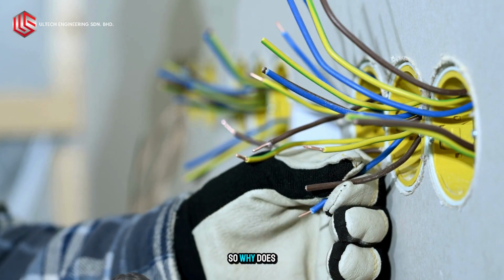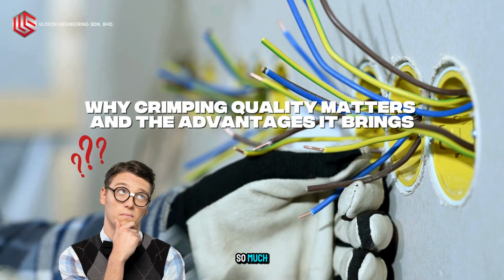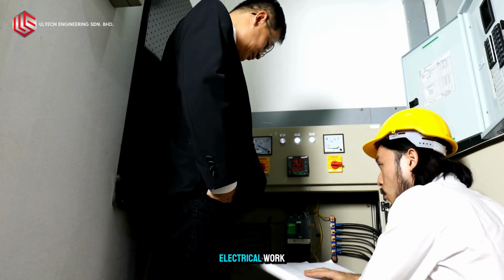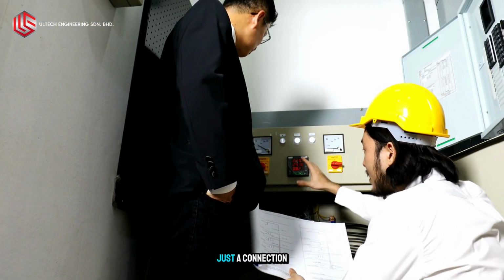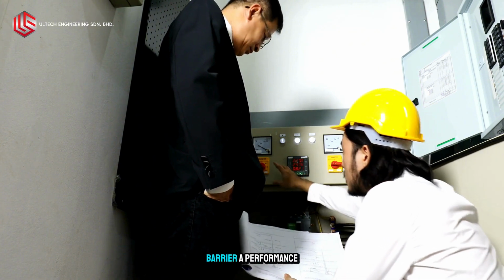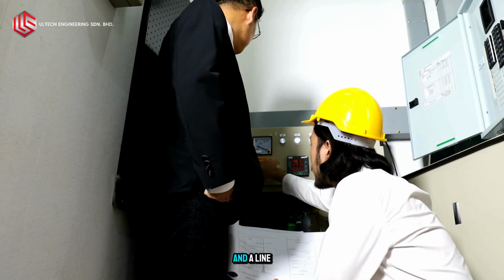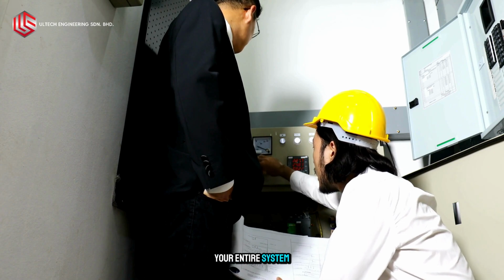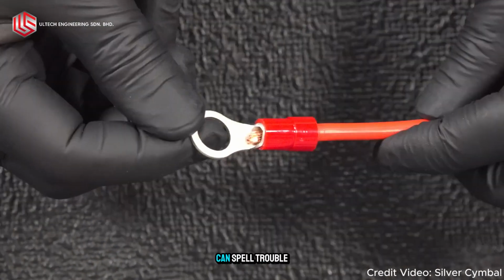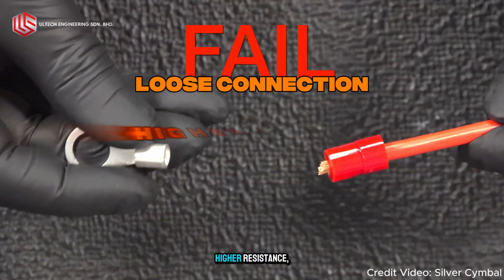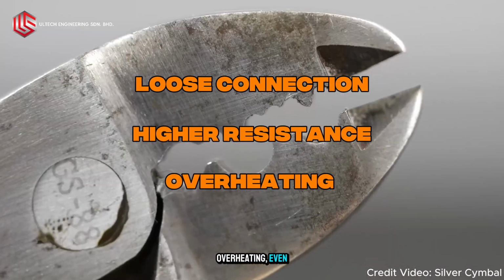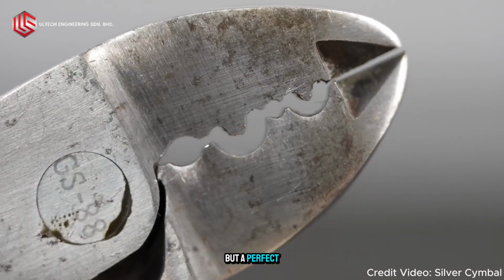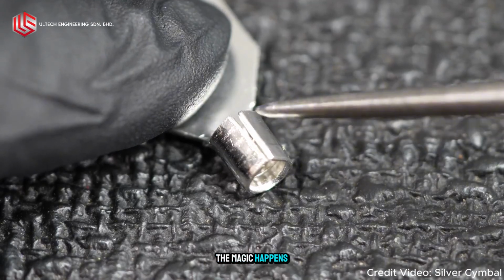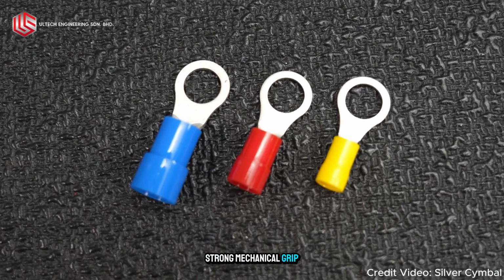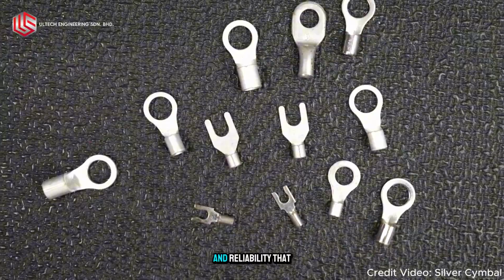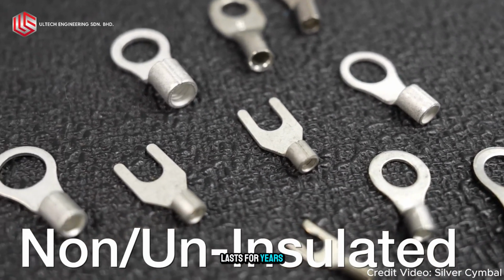So why does crimping quality matter so much? Because in industrial electrical work, a crimp isn't just a connection. It's a safety barrier, a performance guarantee, and a line of defense for your entire system. A poor crimp can spell trouble: loose connections, higher resistance, overheating, even fires. But a perfect crimp? That's where the magic happens. You get a strong mechanical grip, flawless electrical flow, and reliability that lasts for years.